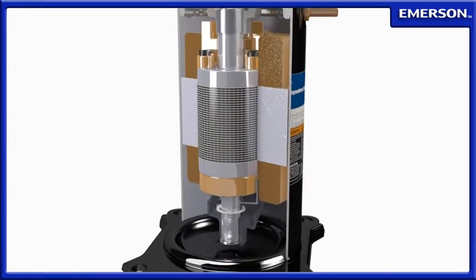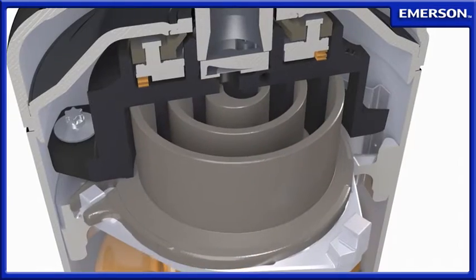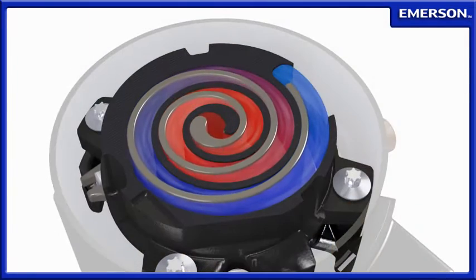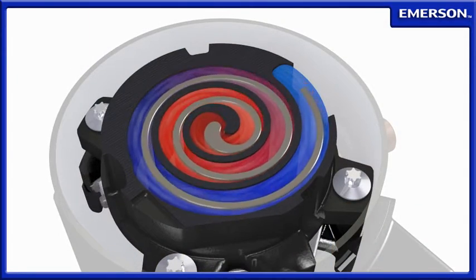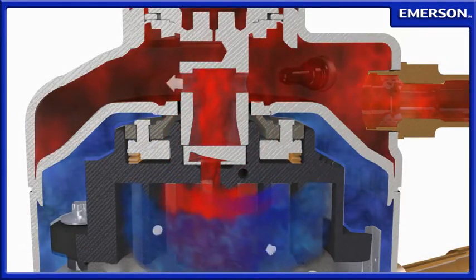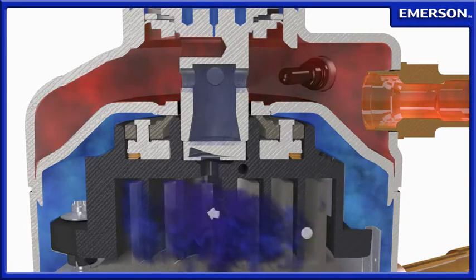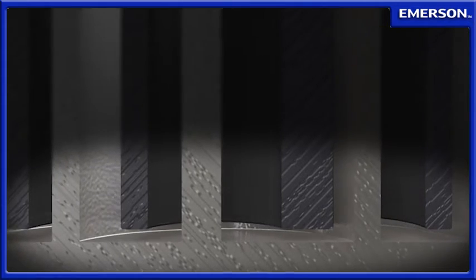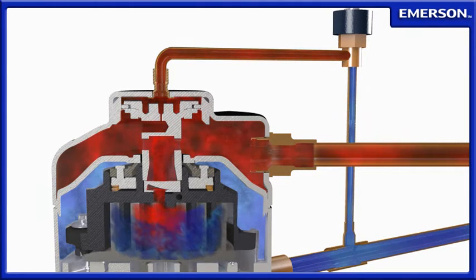For applications requiring precise temperature control, or for those characterized by large variations in load, Emerson Climate Technologies offers an economical solution with the Copeland Scroll Digital Compressor. With digital technology, capacity can be precisely modulated, allowing temperature control to within one-half degree Fahrenheit. The Copeland Scroll Digital Compressor alternates between compression and idling cycles by introducing a controlled internal pressure balance. This pressure balance causes the stationary scroll to move axially. When moved away from the orbiting scroll, this effectively stops the compression cycle. When the pressure balance is reversed, the scrolls re-engage and compression starts again.